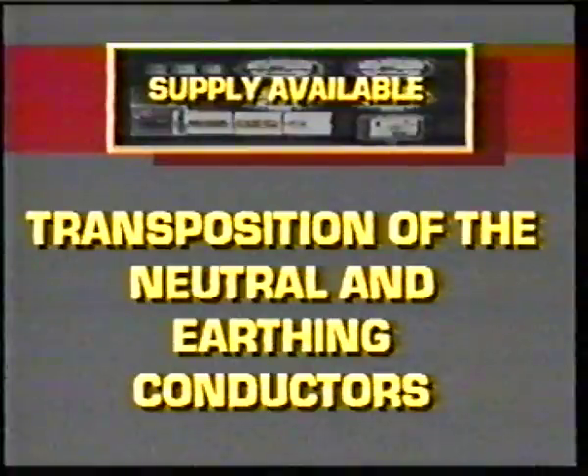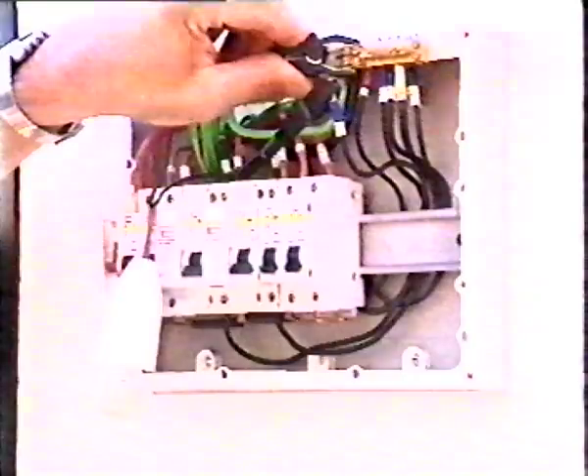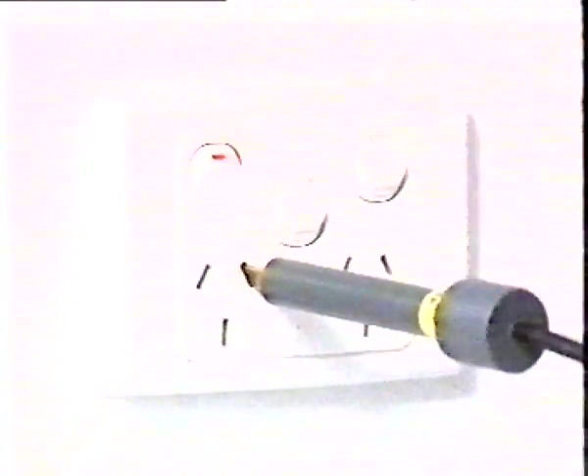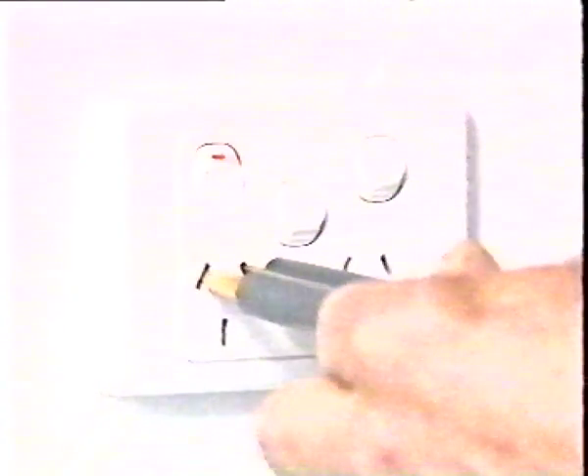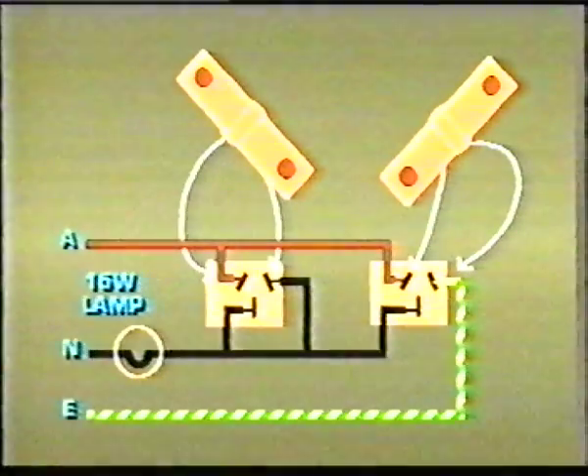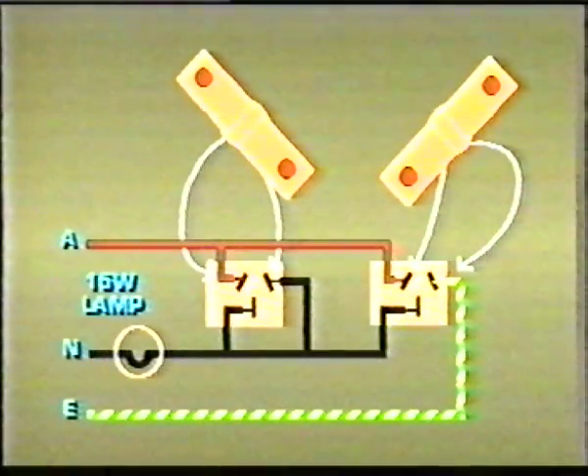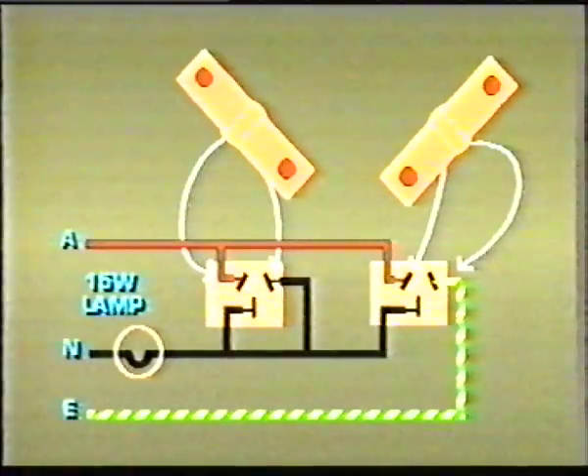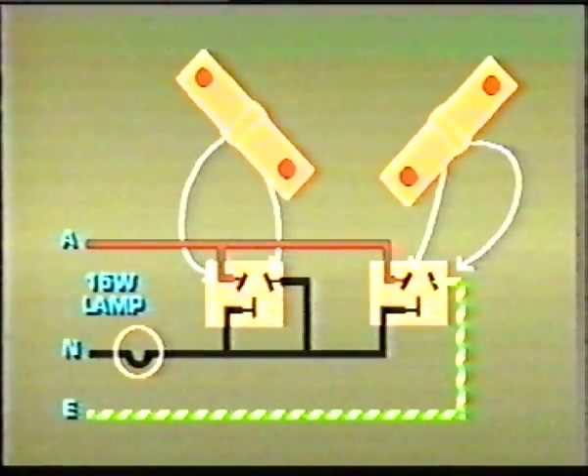Transposition of the neutral and earthing conductors in socket outlet circuits can be tested using test lamps and a 15-watt lamp. Firstly, the neutral conductor of the circuit being tested is disconnected at the neutral link. A 15-watt lamp is then connected between the neutral conductor and the neutral link. The test lamps are then connected active to neutral and then active to earth. Correct polarity is indicated by a dull glow when connected active to neutral and a normal glow when connected active to earth.